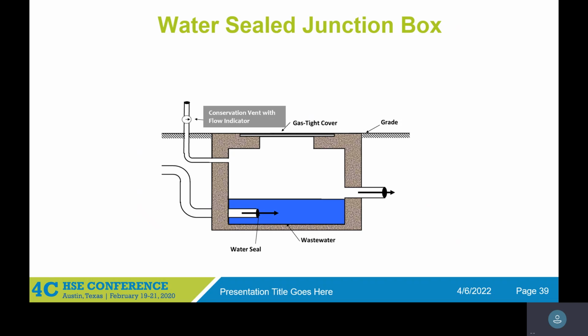You have to have this pipe right here that is 3 feet long and at least 4 inches, but you have to have a flow indicator that shows when there's flow. So either P-traps or everything sealed. And if you use P-traps, make sure you have these flow indicators. Make sense?